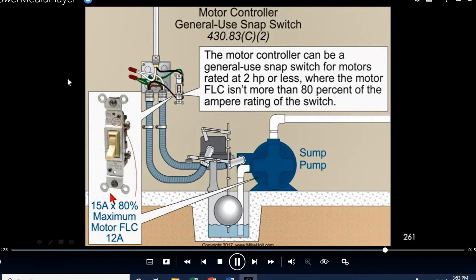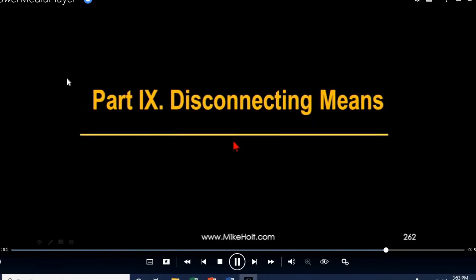Now, a simple toggle switch or general use switch, like a switch right here, can be a general use snap switch for motors rated 2 horsepower or less, where the motor full load current is not more than 80% of the ampere rating of the switch. So if you have a 15 amp rated switch, it says 15 amps at 80% maximum, so a maximum 12 amp motor. So you can use little snap switches for that application. Now this would be the controller in that application. Disconnecting means.